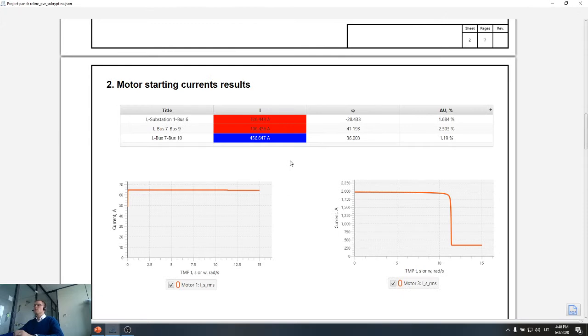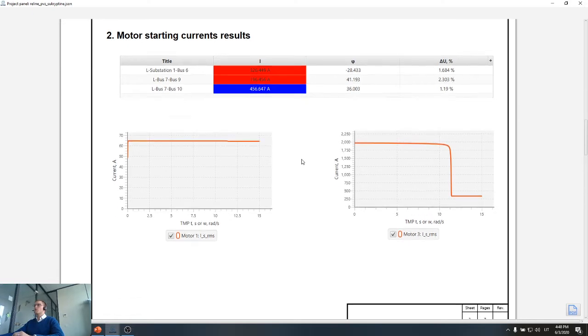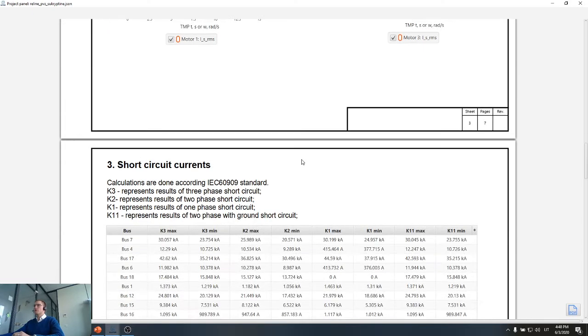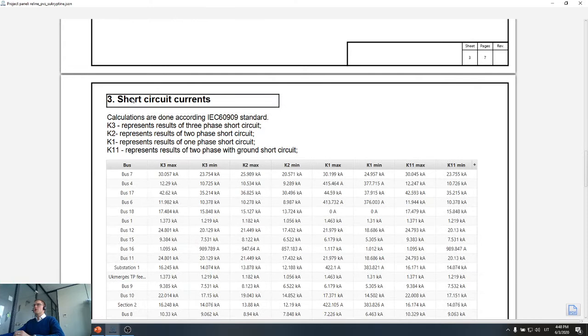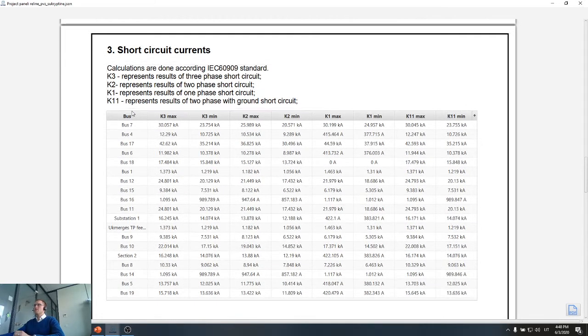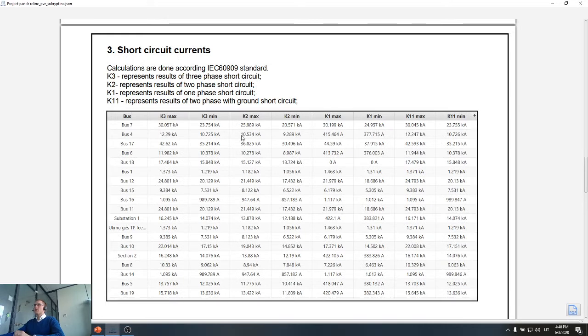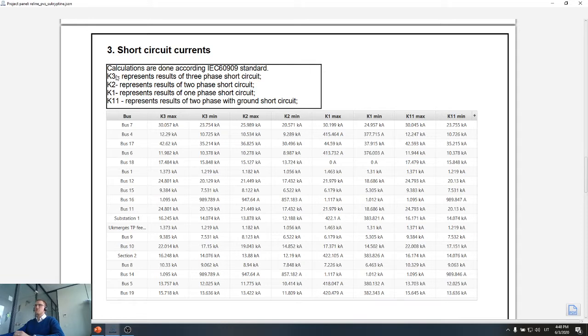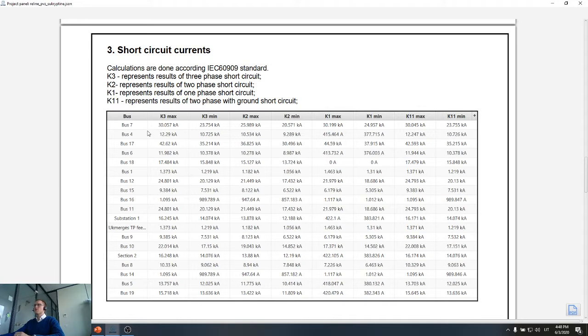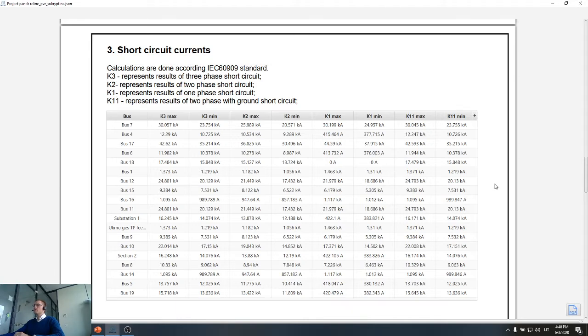You can also prepare something like an example of the report and just change the single line diagram, recalculate the things, and the report will automatically change accordingly. Also, you need to provide information about the short circuit currents, and here I have short circuit currents in maximum and minimum mode in all the possible scenarios. So it's 3-phase, 2-phase, 1-phase, and 2-phase with ground short circuits. So again, this table was added automatically.